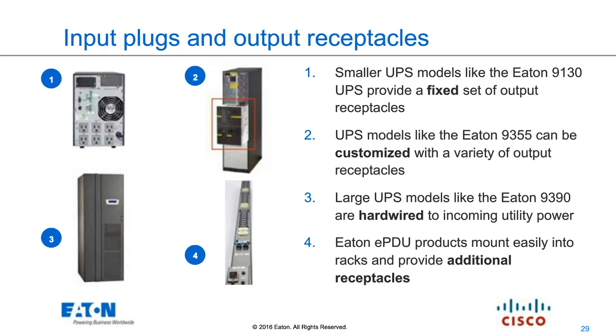I'm going to borrow an answer from Tony on that one: it depends. My generic answer for what UPS to put on a network switch is probably going to be the Eaton 5P or the Eaton 5PX. The biggest difference is the X adds the ability to put external batteries on that system. The reason I say 5P and not something else is that Eaton breaks up our UPS product portfolio into 3 categories based on the level of protection the UPS can provide: a 3 series, a 5 series, and a 9 series. I won't go into all of that right now, but the 5 is kind of the middle of the road, and network switch power supplies are resilient enough that it's hard for me to convince you to buy a premium UPS when a middle-of-the-road UPS will do the job just as well.